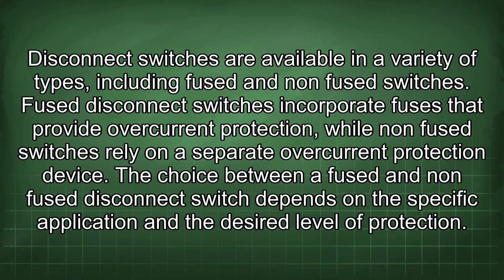Disconnect switches are available in a variety of types, including fused and non-fused switches. Fused disconnect switches incorporate fuses that provide overcurrent protection, while non-fused switches rely on a separate overcurrent protection device. The choice between a fused and non-fused disconnect switch depends on the specific application and the desired level of protection.